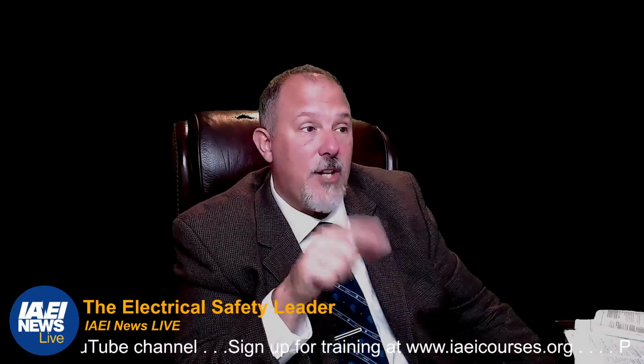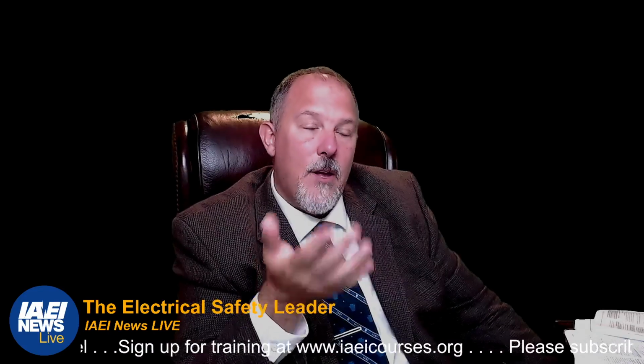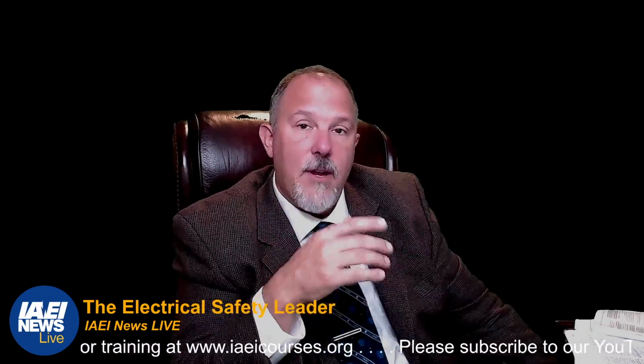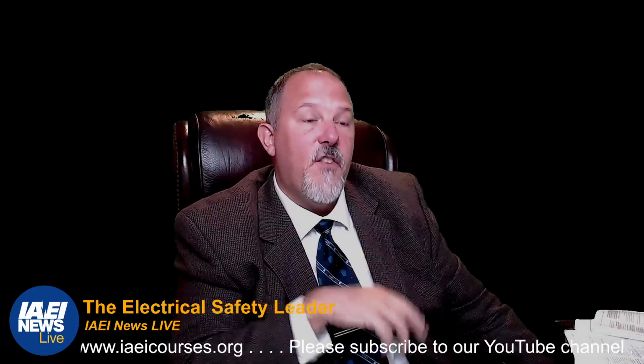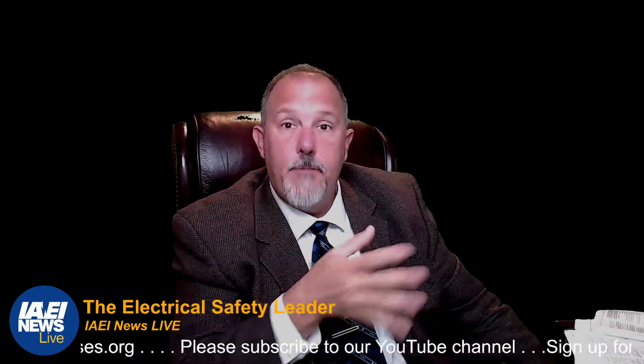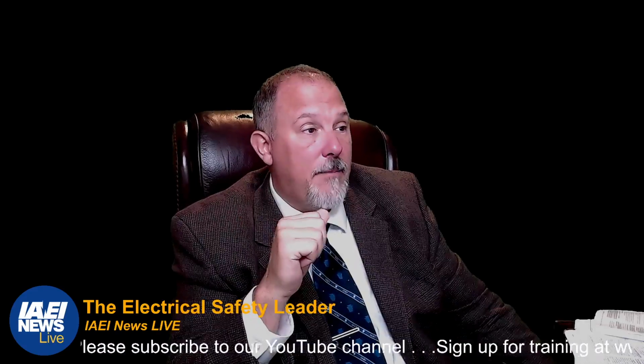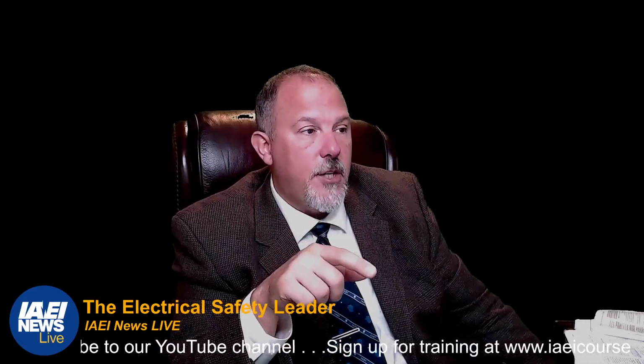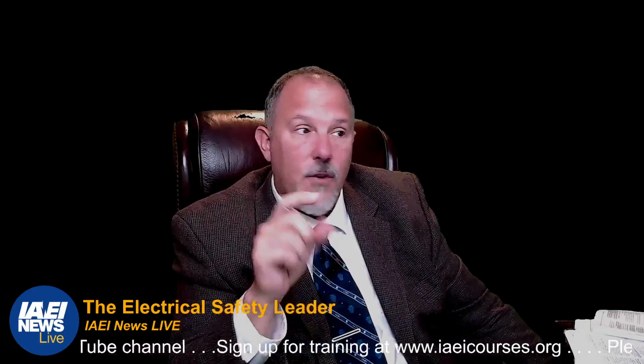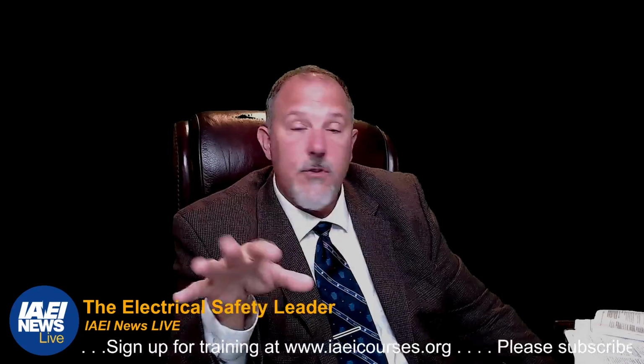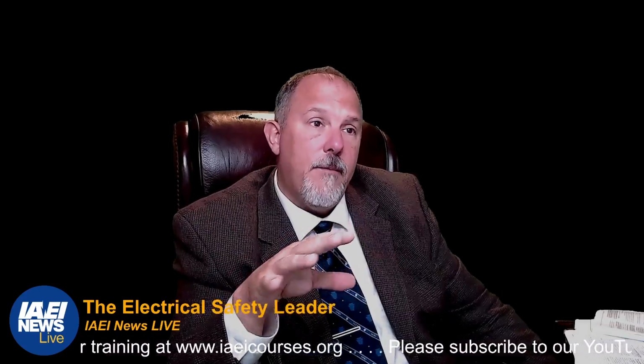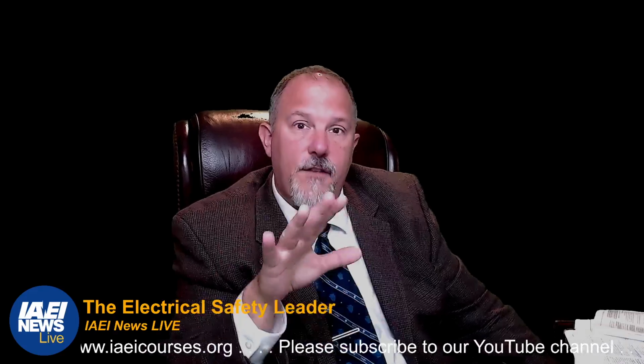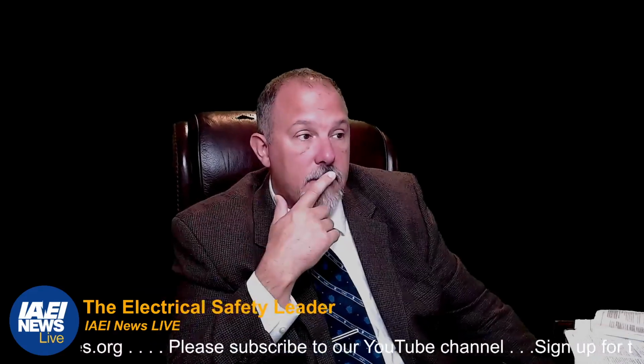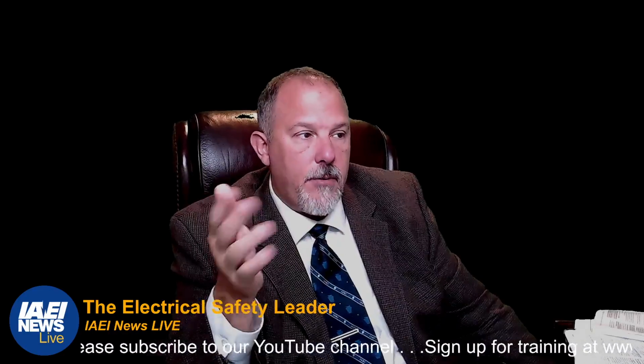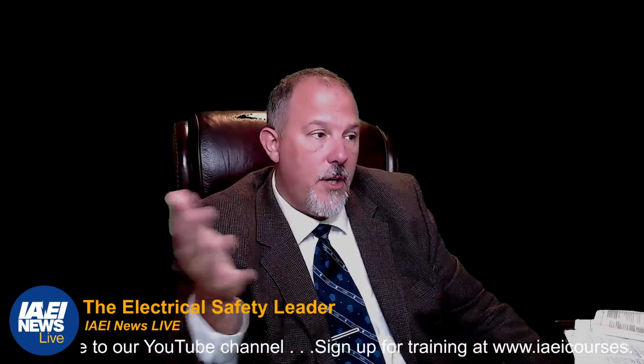For connected communicating addressable devices, verify the device addresses are set in accordance with the documentation. Why? What does that have to do with the panel board? Well, if you don't have those devices, you're not protecting the conductor. If you're not protecting the conductor, you can have overheating, and then boom, unintended rapid disassembly in the field. Verify instrument transformer ratios. Inspect the insulators for contaminations. Verify any filters. So you might have filters installed where you want airflow going through, but you need to filter out depending upon the environment. Verify barriers are in place. Visually inspect the environmental controls and all that jazz.